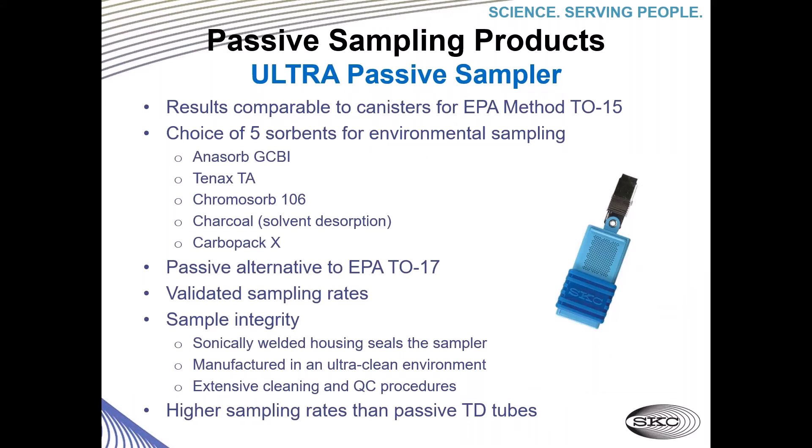The last sampler I want to highlight is the Ultra Passive Sampler. Lab results for the Ultra are comparable to canisters for EPA method TO-15, yet there are no cleaning and certification costs. The price is significantly lower, and because of the size and weight, there are no expensive shipping costs either. You have a choice of five sorbents for environmental sampling, providing a nice passive sampling alternative for EPA TO-17, with no pump, tubing, or calibration required. These samplers are sonically welded and manufactured in an ultra-clean environment to protect sample integrity. The Ultra also boasts higher sampling rates than passive thermal desorption tubes.